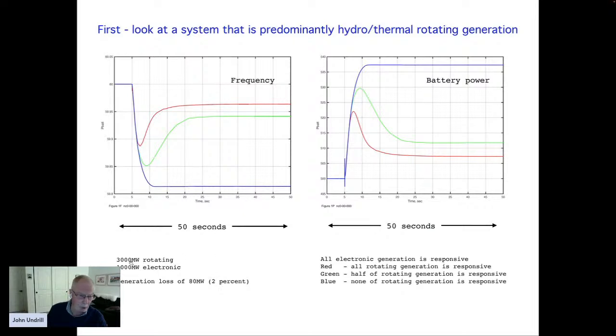So 3,000 megawatt, 4,000 megawatt system, 80 megawatt load increase, which is 2%. That's a very large disturbance in relation to the normal operation of, let's say, the Eastern or Western USA grid or Western European grid. It would be a large event in relation to the two large grids that exist in the Russian world. And it would be a very large event in relation to any of the state electricity board systems in India or the electric system of China.